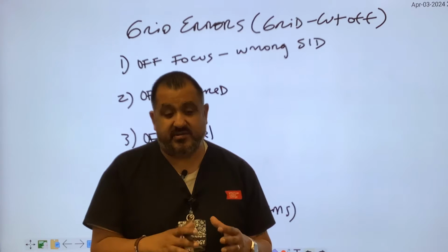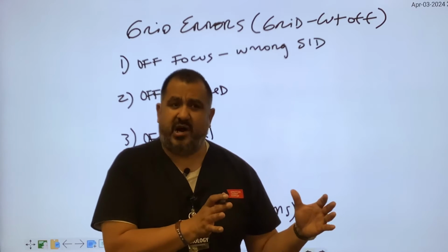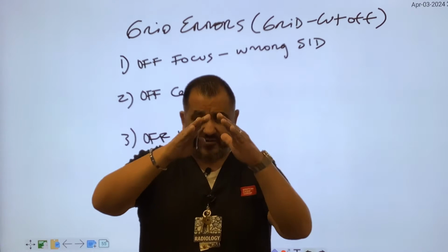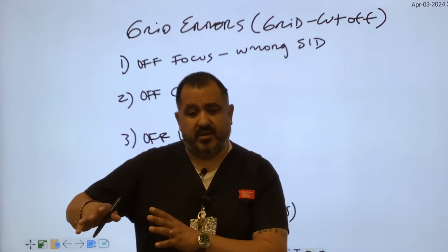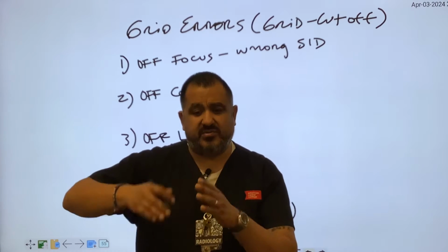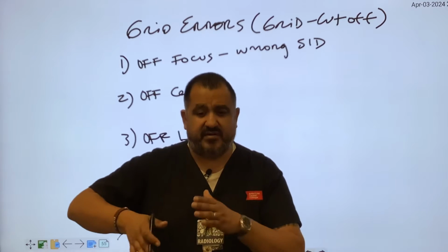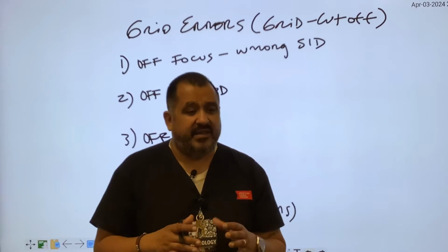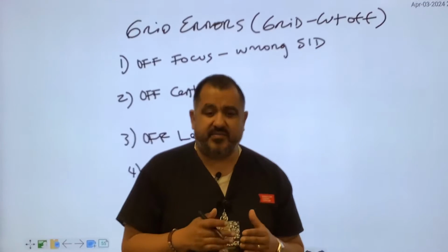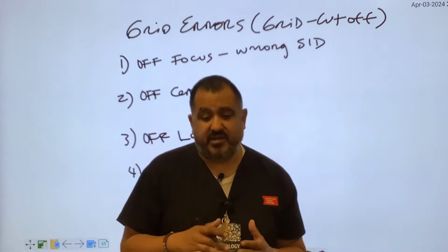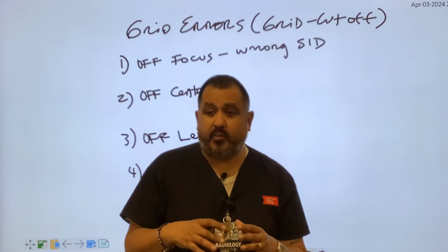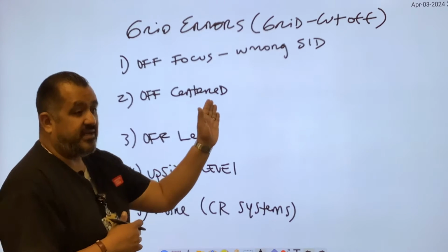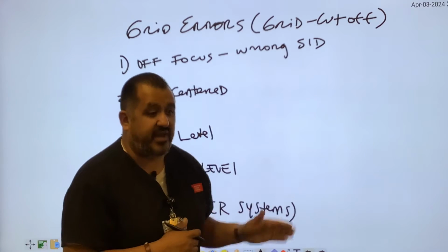Off-centered grid error is where you have the body part not centered to the receptor, or you can have the body part centered to the receptor, but the grid is off. Remember the divergence of the X-ray beam. The lines of the photons themselves are going to be absorbed by the grid lines because it's not centered. These grids are specifically designed to be used at a certain distance and at the center point of the grid itself. So if your grid is not centered to the central ray...